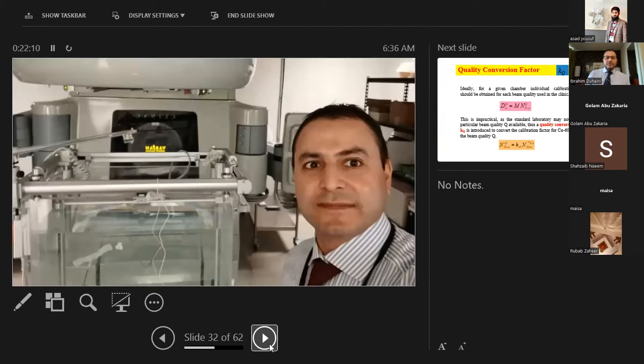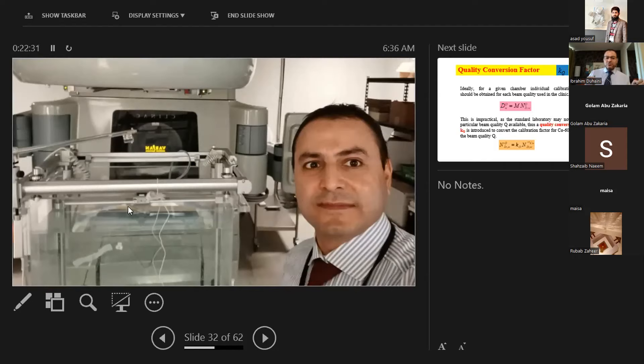Setting up the water phantom is critical — it may take more than an hour to level it correctly, but a good measurement starts with a good setup. If the water phantom is leveled, the ion chamber will be leveled and measurements will be accurate. Taking time to set up properly saves time from having to repeat measurements.